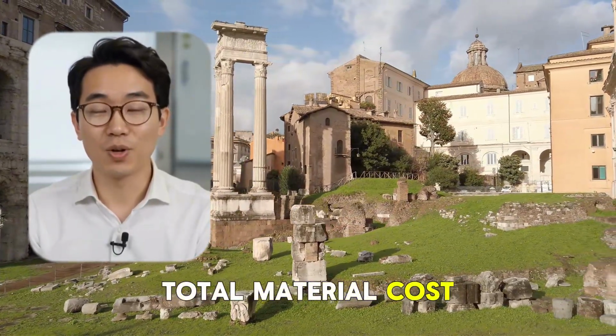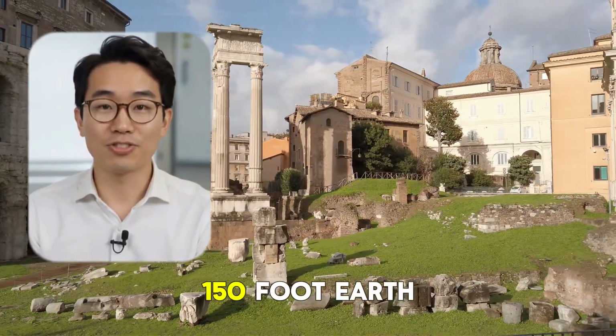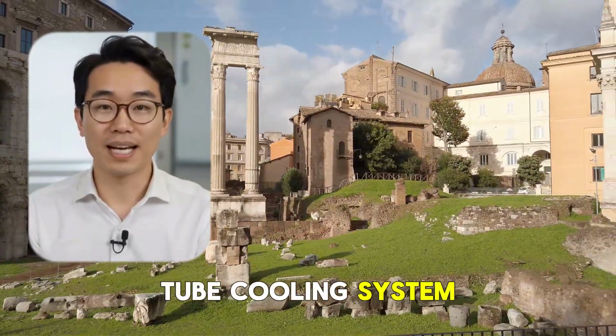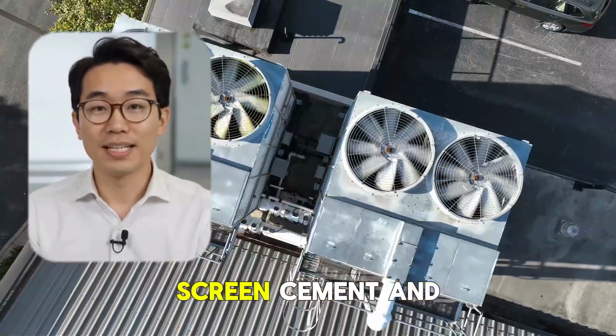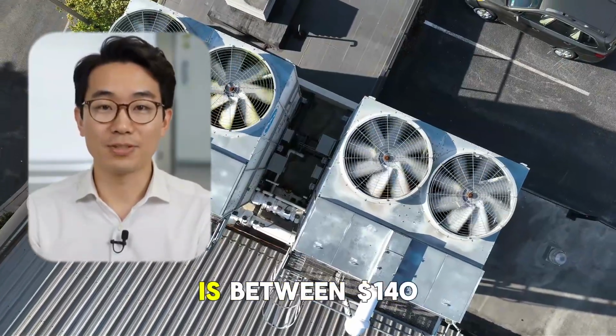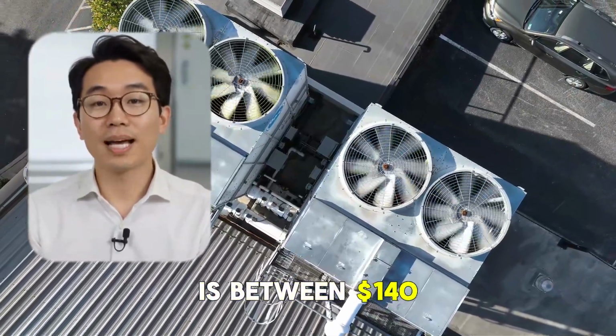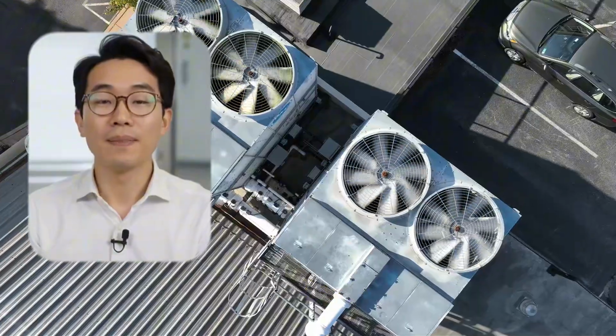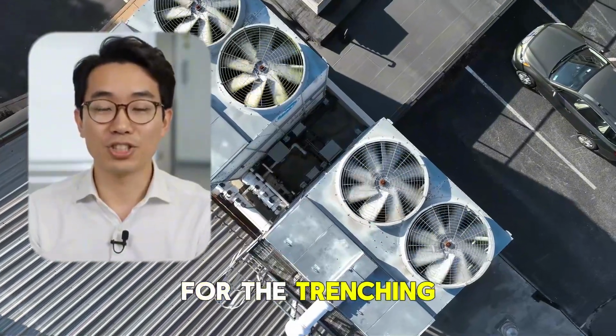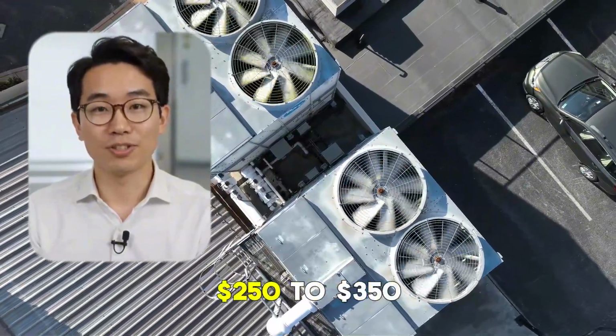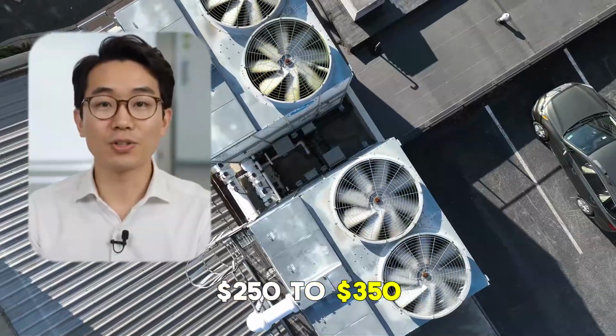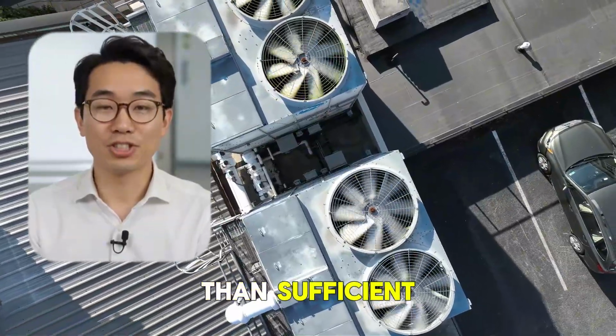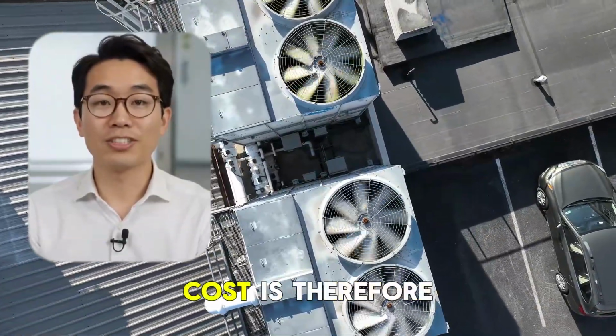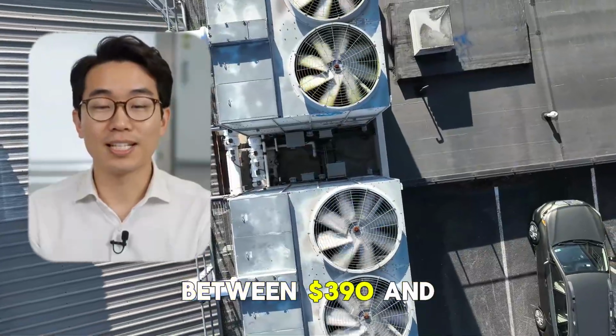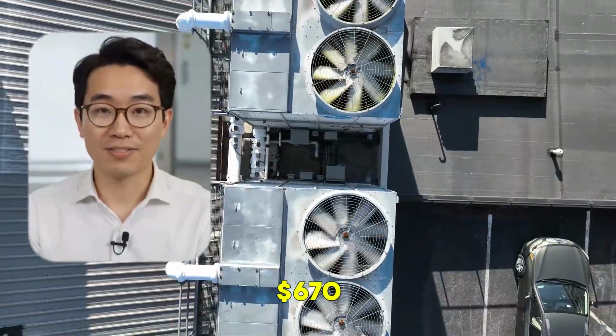Your total material cost for a complete 150-foot earth tube cooling system, including pipe, fittings, screen, cement, and drainage stone, is between $140 and $320. If you rent a mini excavator for the trenching, that runs approximately $250 to $350 for a single day, which is more than sufficient. Your total installed cost is therefore between $390 and $670.